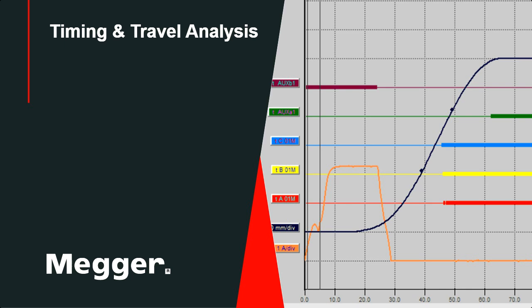This can also refer to a specific point in time or specific period within the operation. And the main factor is that the time measurement is relative to time zero. There is no speed measurement. If there are any resistor contacts, either pre or post in line, the timing is still measured the same way, and it does include the measurement for the resistance of those resistors.